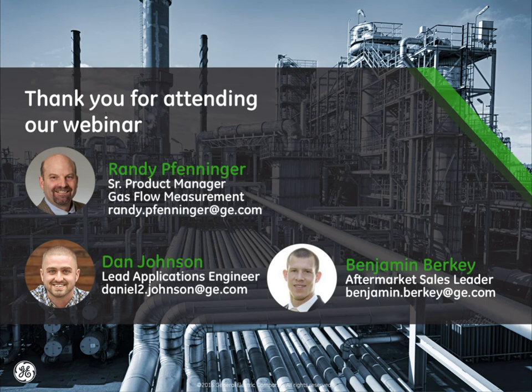So here at GE, we have a couple of different types of flare evaluations, we'll call it. Through NSPS Ja, because the regulation was very focused on the meter sensitivity, we were able to evaluate the flow meters based on the process conditions at that refinery and provide them a statement of compliance or non-compliance. This allowed the refineries to then come back to GE and potentially upgrade their meters such that the sensitivity met the requirements of the regulation.